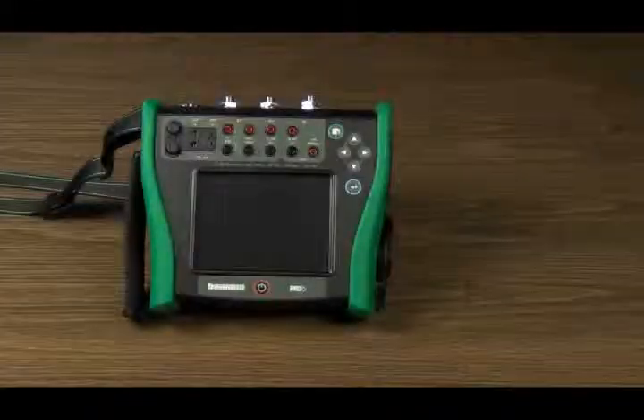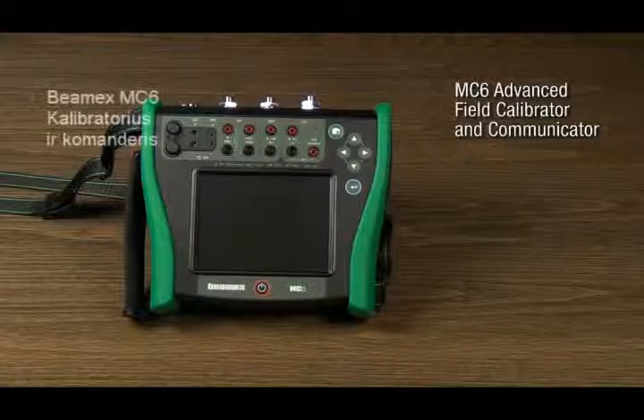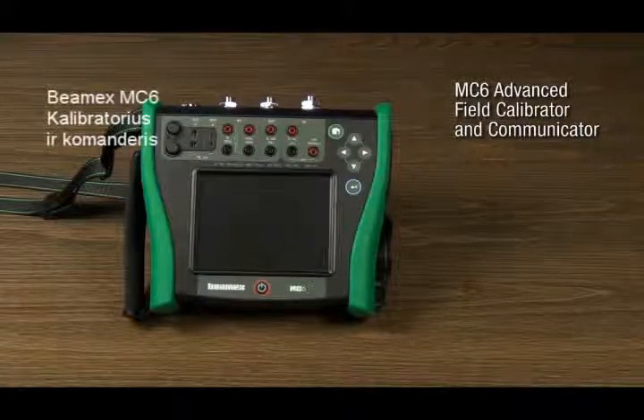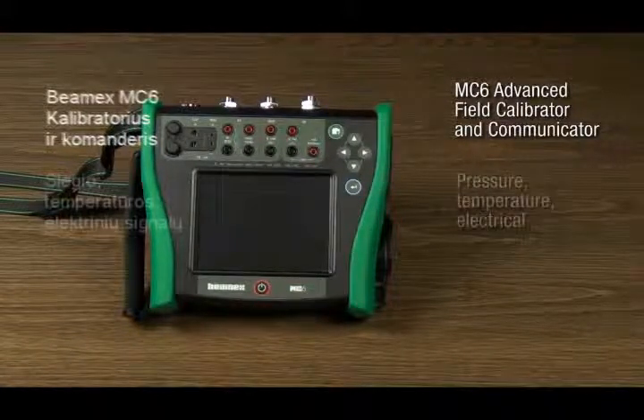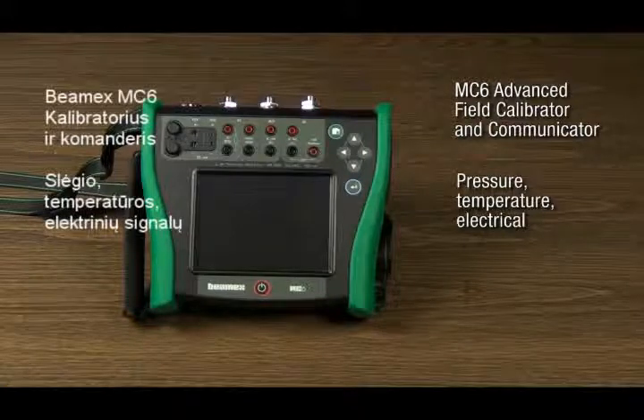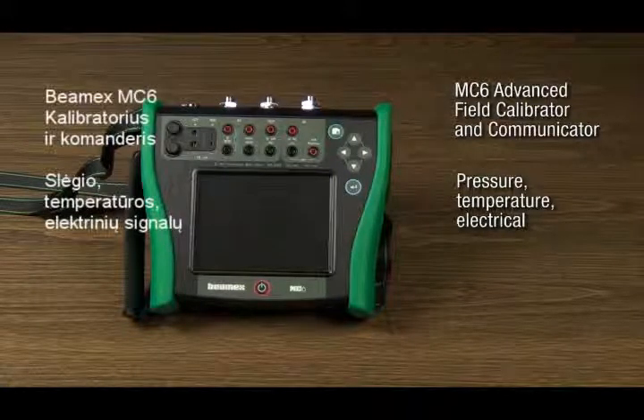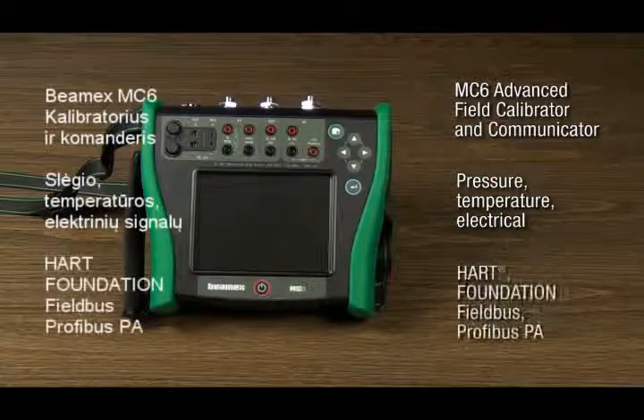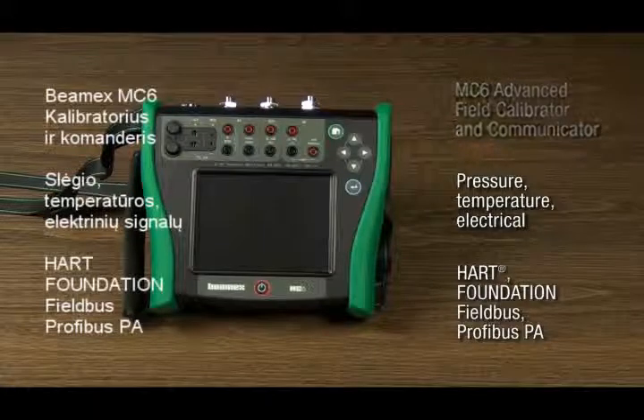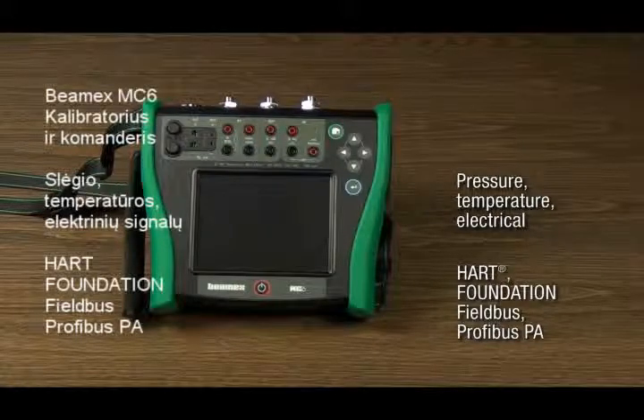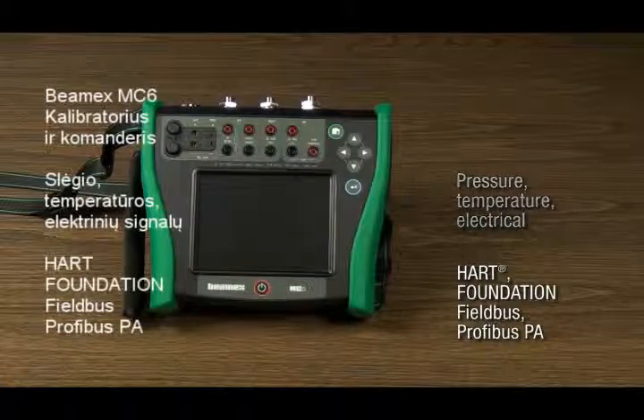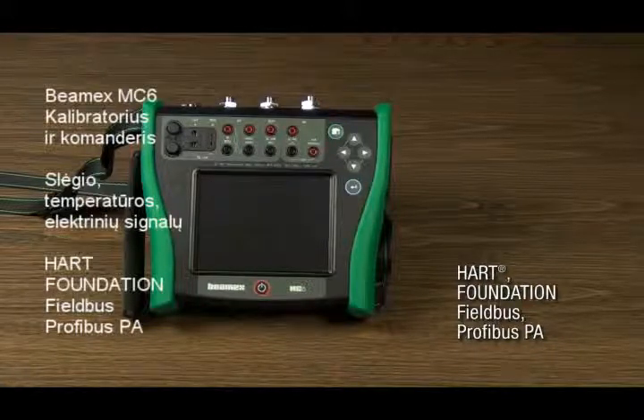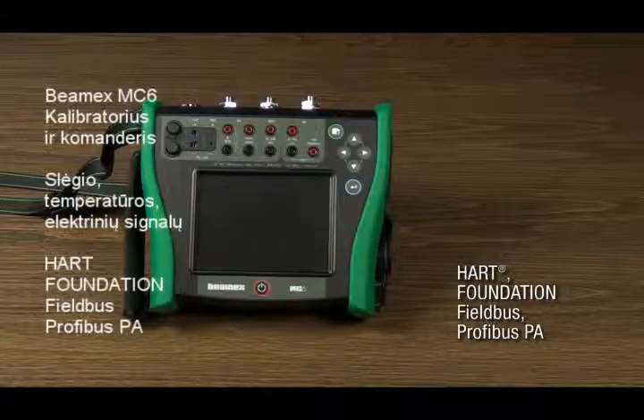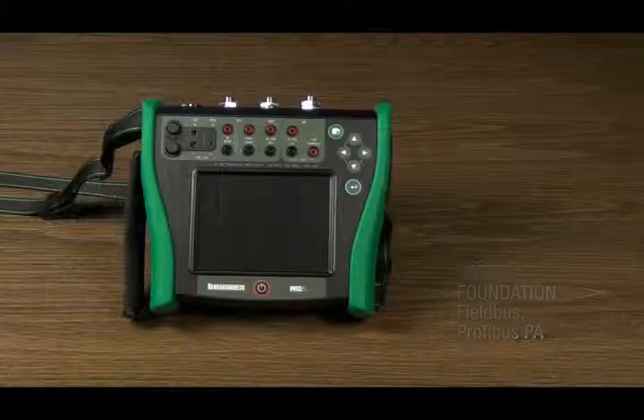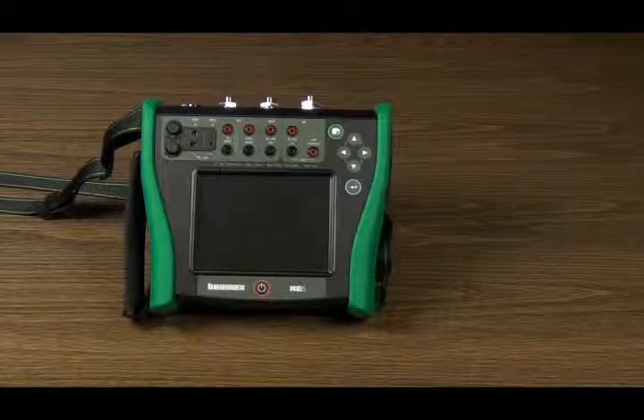The Beamex MC6 is an advanced field calibrator and communicator. It offers calibration capability for pressure, temperature and various electrical signals. The MC6 also contains a full fieldbus communicator for HART, Foundation Fieldbus and Profibus PA instruments. The MC6 main features include accuracy, usability, versatility, communicator functionality and integration to the Beamex integrated calibration system.